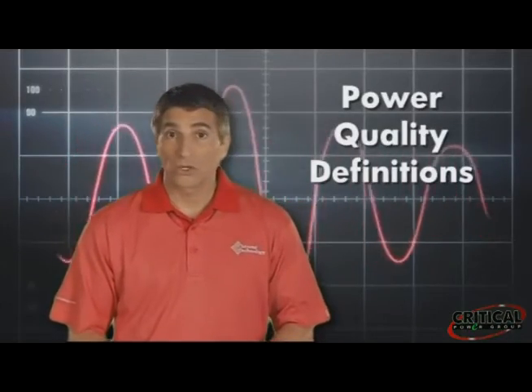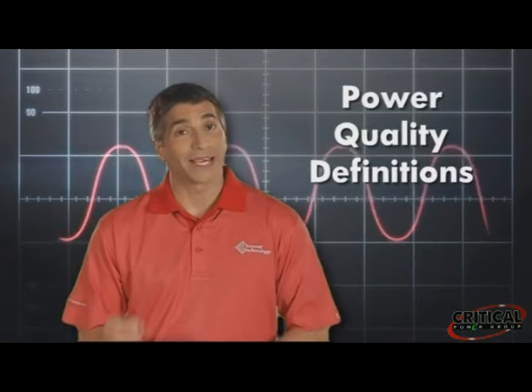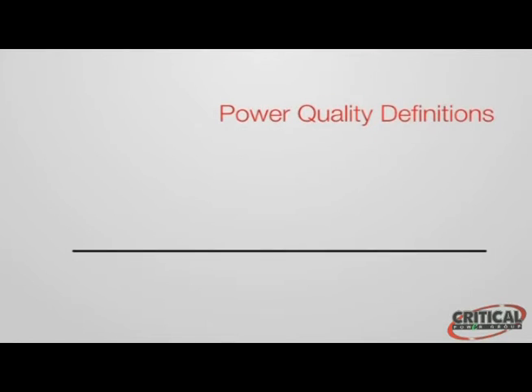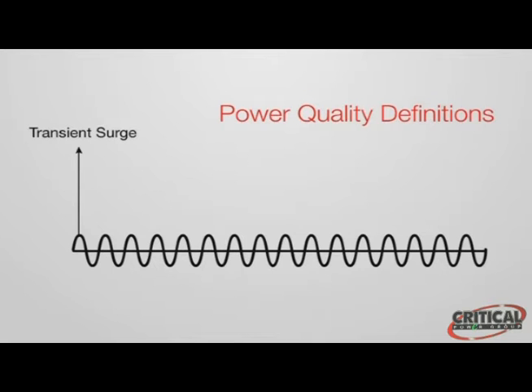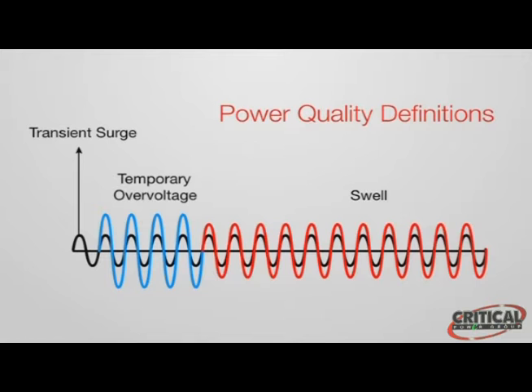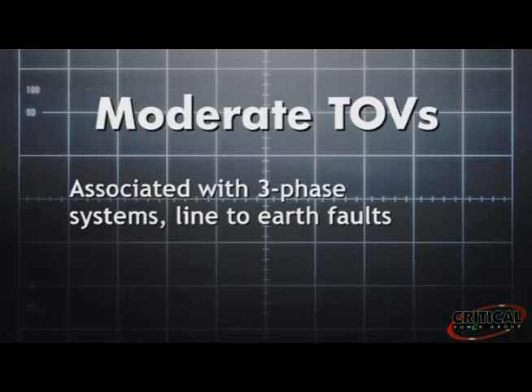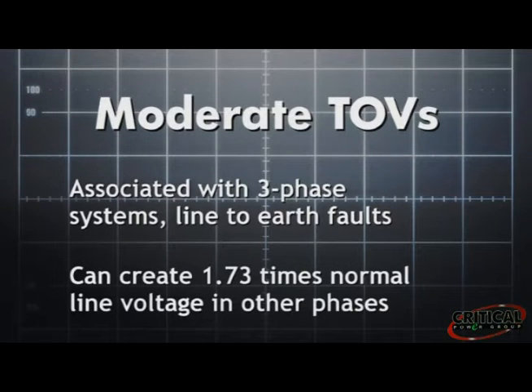Now let's talk about power-quality events that last longer than transient surges. Transient surges last from 1 nanosecond to 100 microseconds. A surge that's 1.8 to 2 times the nominal voltage and lasts from 100 microseconds to 8 milliseconds is called a temporary overvoltage, or TOV. A swell lasts from 8 milliseconds to a full minute at 1.1 to 1.8 times the nominal voltage. Moderate TOVs are associated with three-phase systems and line-to-earth faults, and can create 1.73 times the normal line voltage in other phases.